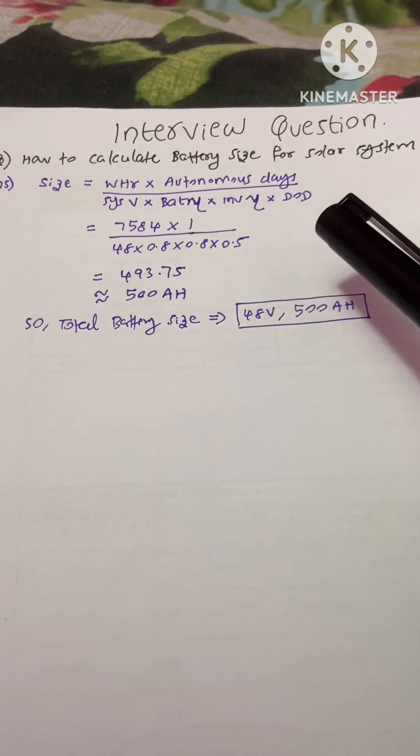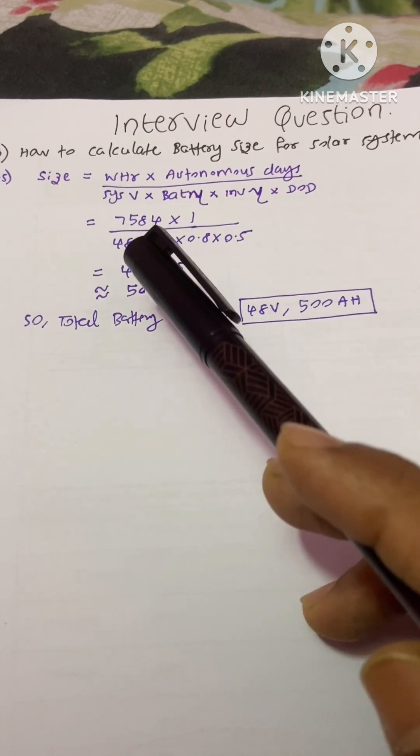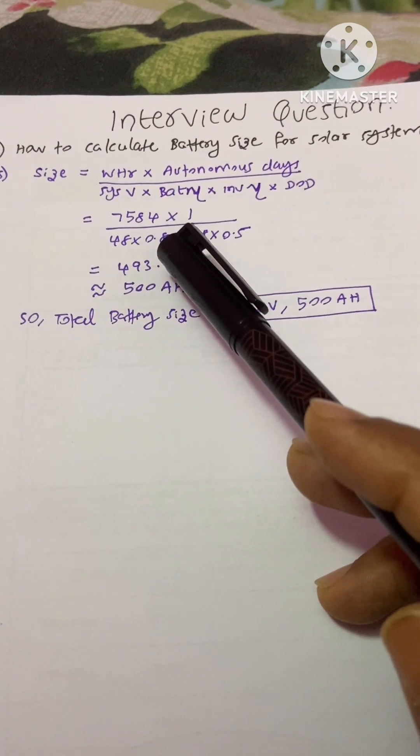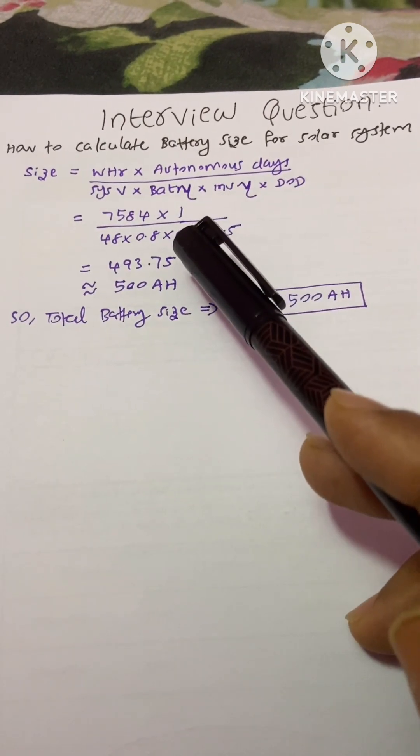Suppose in your country you would get sunlight in whole seven days per week, then you need to put in one. Here our watt hour is 7584, system voltage is 48, and battery efficiency is 80%, that is 0.8.